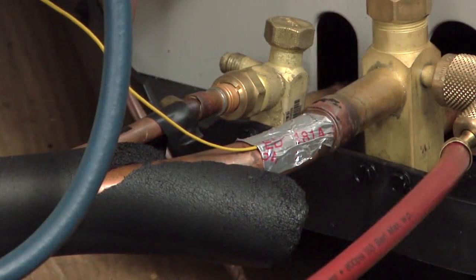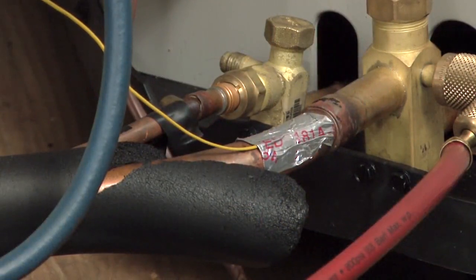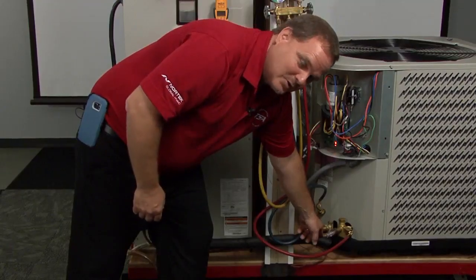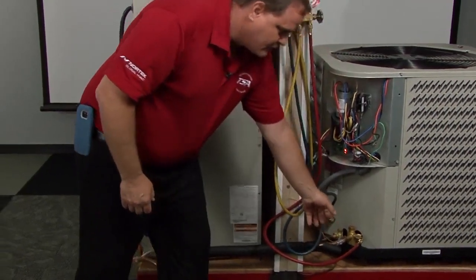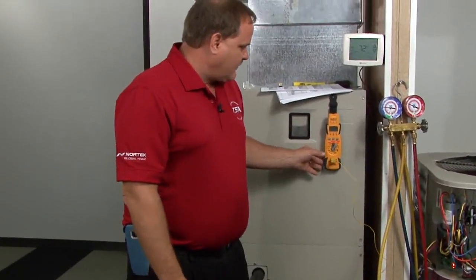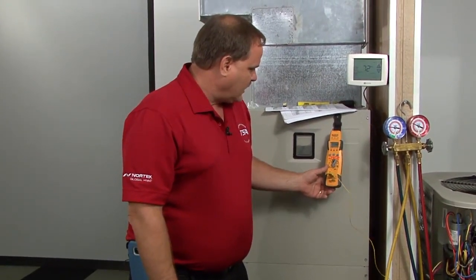And then obviously in heating mode, this should get really warm, especially with the temperature inside this room. Just to give you an idea here, it hasn't been on very long. I'm at 114 degree discharge temperature. Like I said, this is not the ideal location to be running this unit. It's inside a room, the indoor and outdoor units both in the same room. But I just wanted to show you just briefly. But that's how you would do it if you're checking the charge using the discharge temperature. Just hook your thermocouple on there.